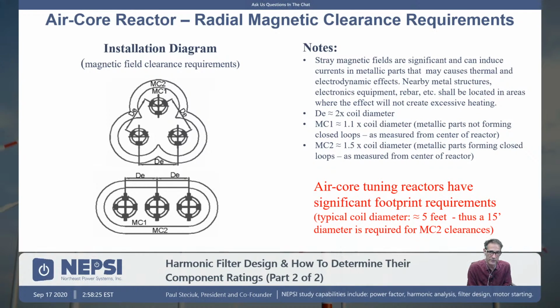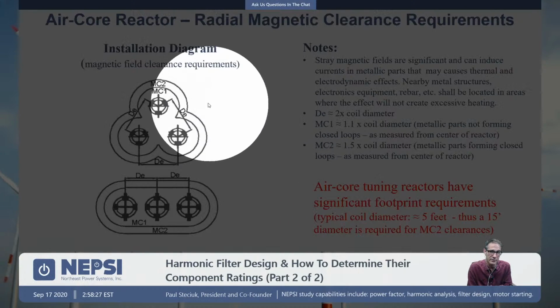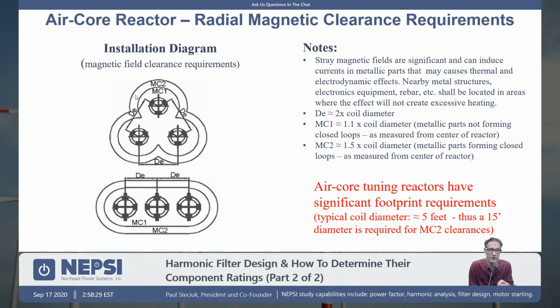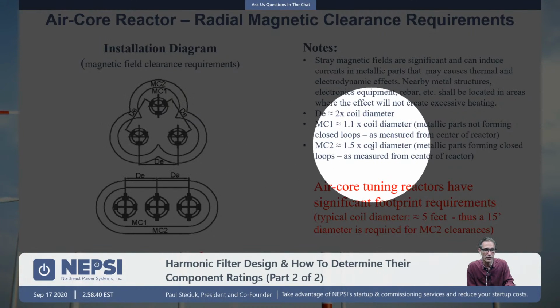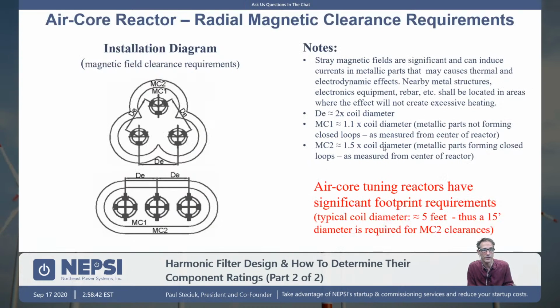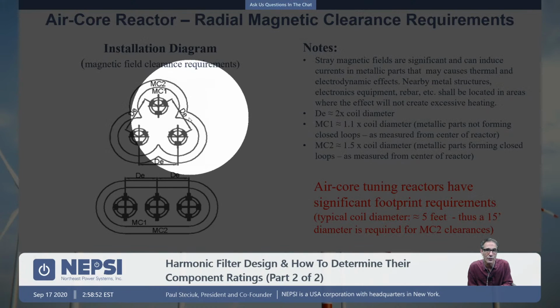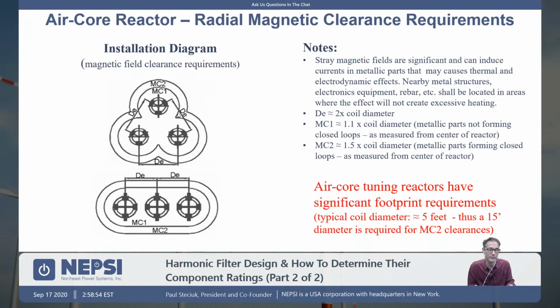When you specify air core reactors, you're going to get drawings back that have the magnetic field clearance lines, this MC1, MC2 line. And that distance is going to be quite big. In fact, it can be up to 1.5 times the coil diameter. So it would be no metallic parts forming closed loops within that 1.5 times the diameter. So this area here, realistically, sometimes can be 20 feet across, so it can be quite significant.